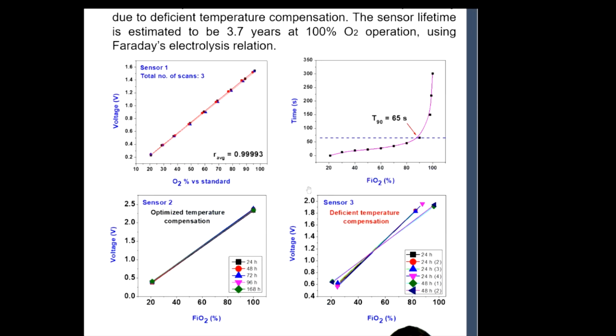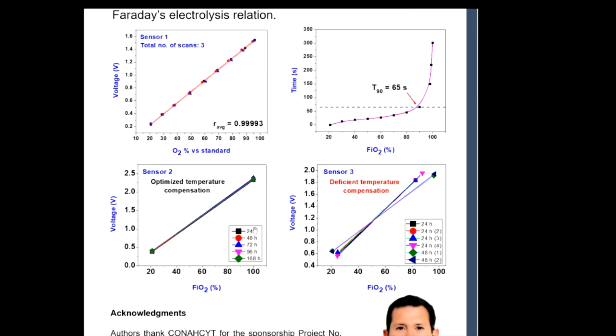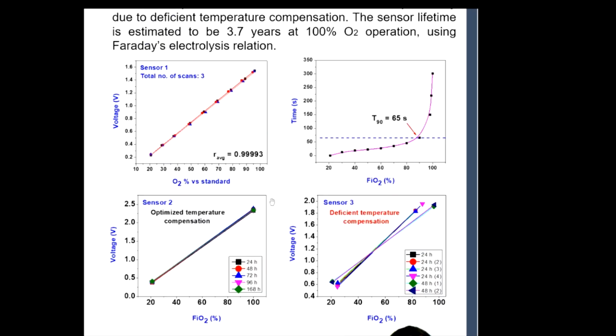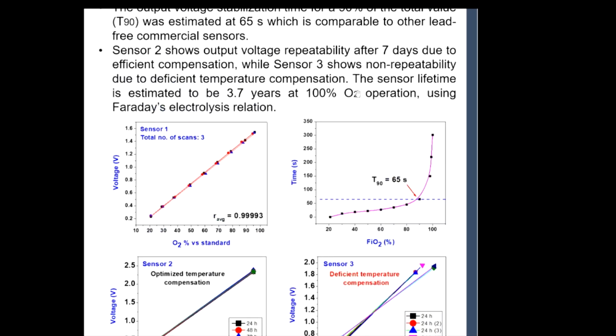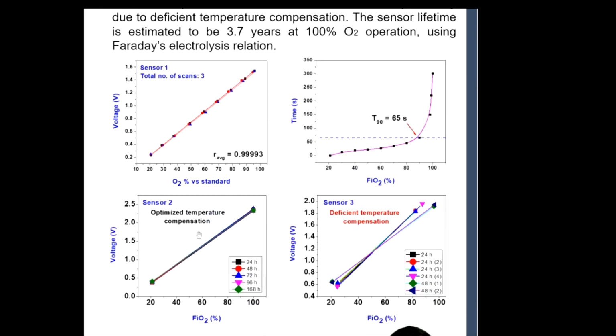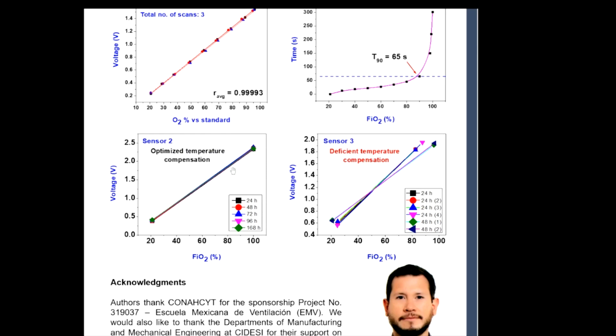Finally, we determined the repeatability of these sensors in the mechanical ventilator system. Here we made measurements after 7 days, and we can see in the figure that there is repeatability in this voltage value, and this is mainly due to having an optimized temperature compensation through thermistors. If we have a deficient thermistor arrangement in the PCB signal conditioning card, we have deficient temperature compensation, and we do not observe this signal repeatability.